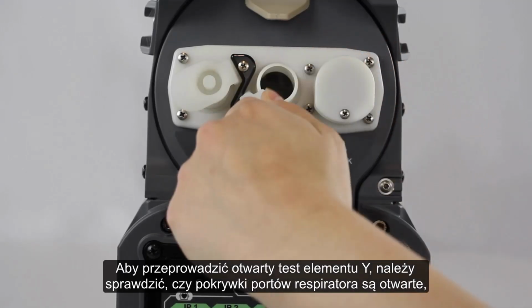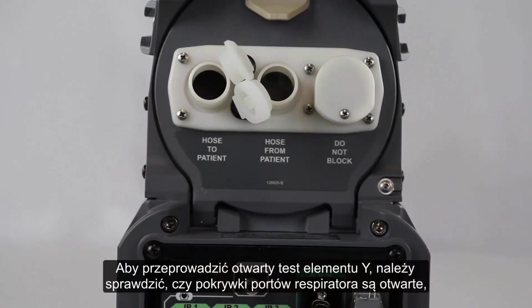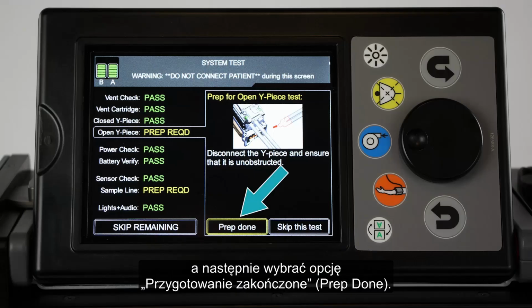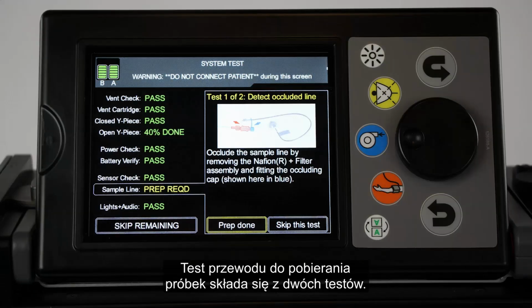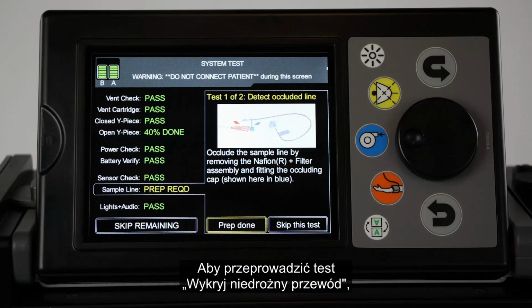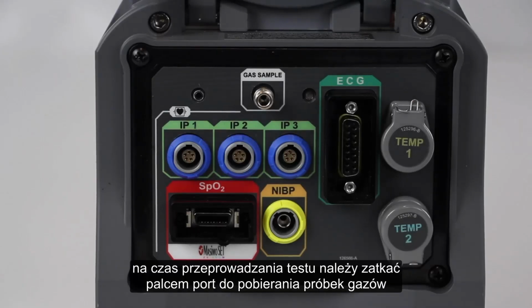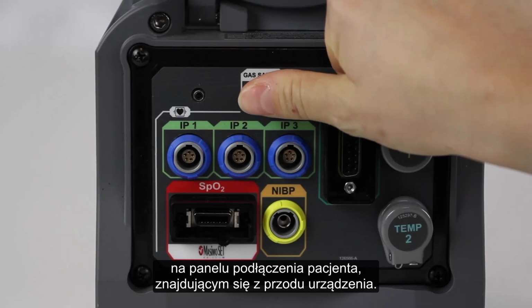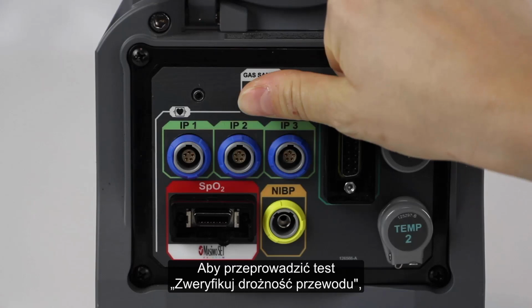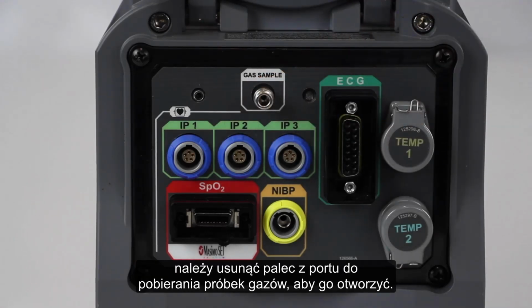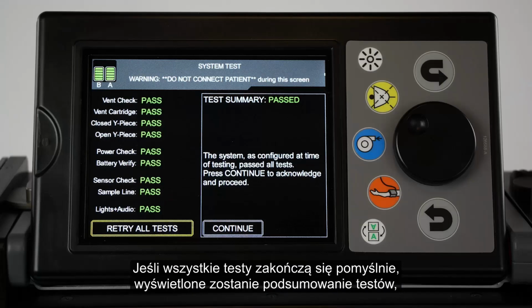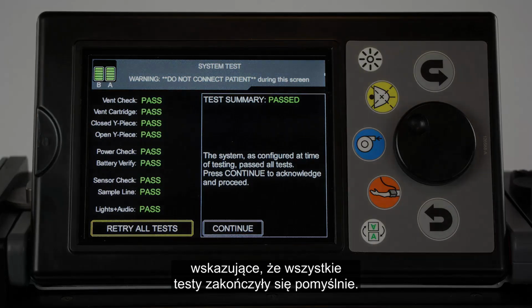To complete the open Y-piece test, ensure that the ventilator port covers are open, then select Prep Done. The sample line test is comprised of two tests. To complete the Detect Occluded Line test, occlude the gas sample port on the patient connections panel at the front of the device with your finger until the test is completed. To complete the Verify Clear Line test, remove your finger from the gas sample port and leave it open. If all tests are successful, a test summary is displayed, indicating that all tests have passed.